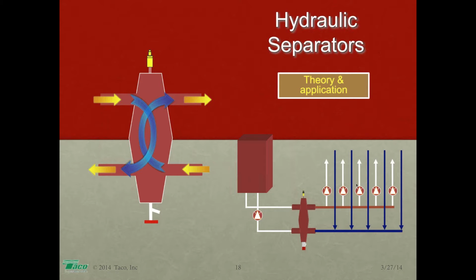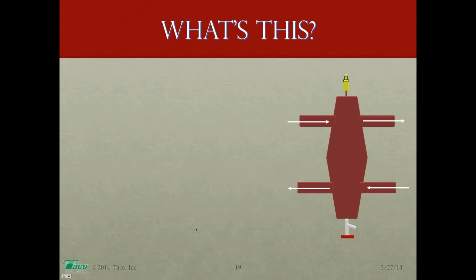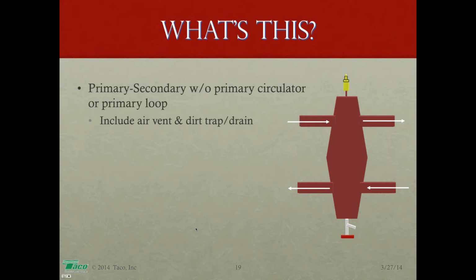A hydraulic separator, and we've seen them all over the place, is really nothing more than a prefabricated short fat header, if you want to look at it that way. It's just a short fat header that has been made for you. You could build it, or you could buy one and bang it on the wall and save time. Your call. Really what you're doing here is primary-secondary, without a primary circulator or a primary loop, so to speak. These will have an air vent up at the top, a little dirt trap down at the bottom for the reasons we discussed earlier.